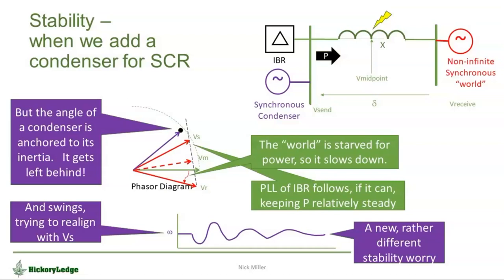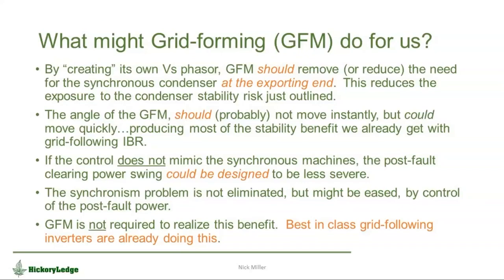Not necessarily. It's a concern. It's not fatal. So now let's ask the question, what might happen as we move on from fixing the problem with synchronous condenser to fixing it with grid forming? By having a grid forming inverter, I ought to be able to not have to support that sending end voltage to keep the control stable. That was the whole point of that.